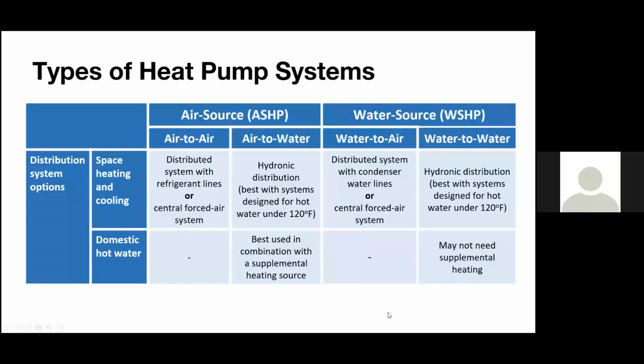But on the other end, they heat or cool water, and then from there you can really do whatever you want with it in the building. You can put it through radiators, put it through air handlers, really whatever you need. Then the next level on this is the heat recovery versions of those chillers. They're becoming quite popular as well. You can handle some of the domestic water, and that's because they don't need to go extract heat from 0 degrees outside. They're extracting it from, say, 50 degree geothermal loops. So they tend to be better at generating domestic hot water.